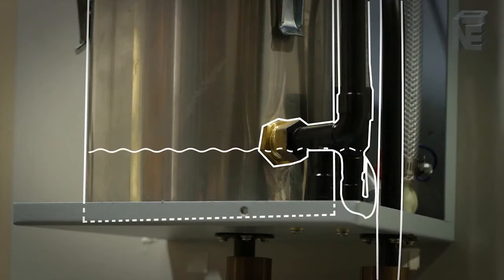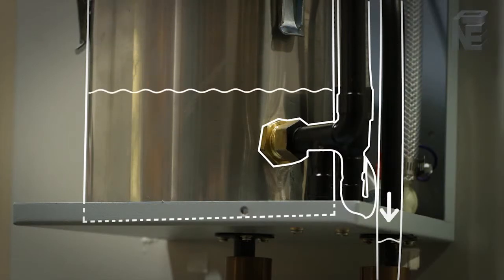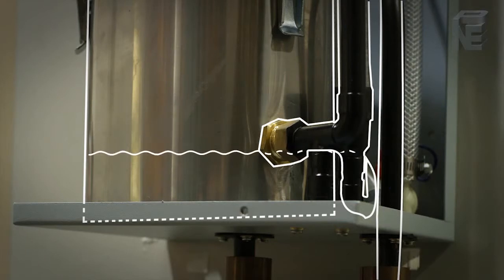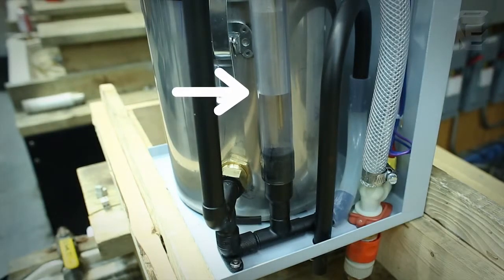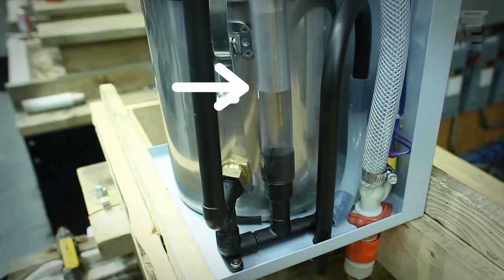There is no drain valve. The humidifier will automatically fill again with water and siphon the chamber a second time. The level of water in the cylinder can be seen in the clear silicone hose, which houses the level probes, to the right of the boiling chamber.